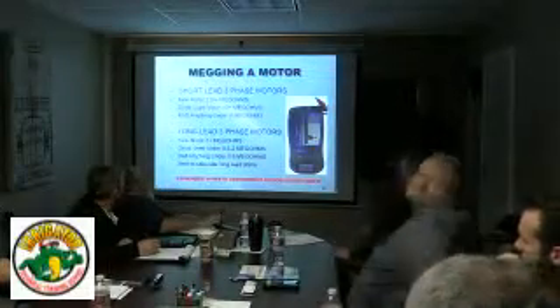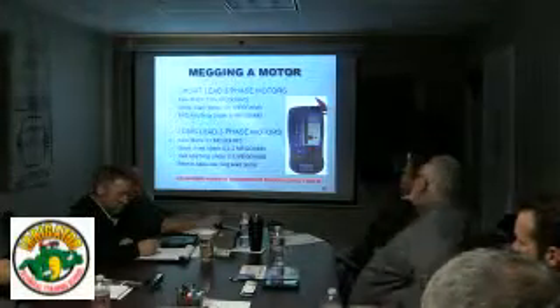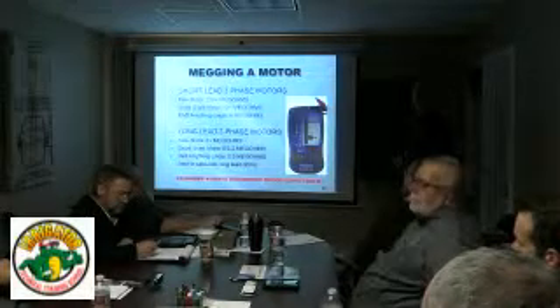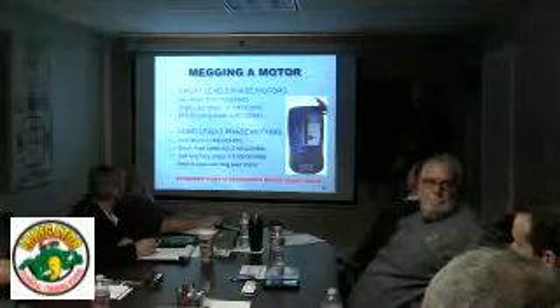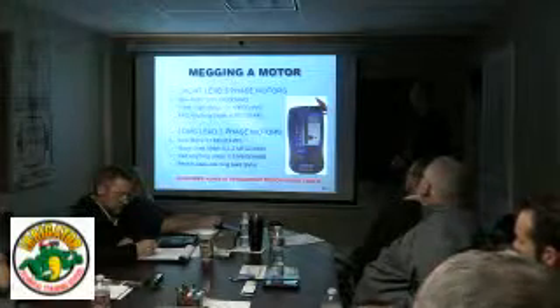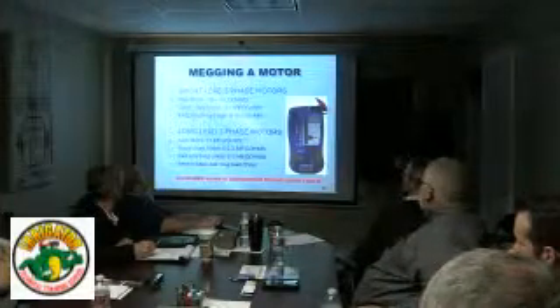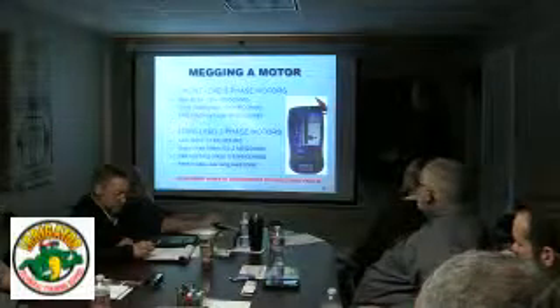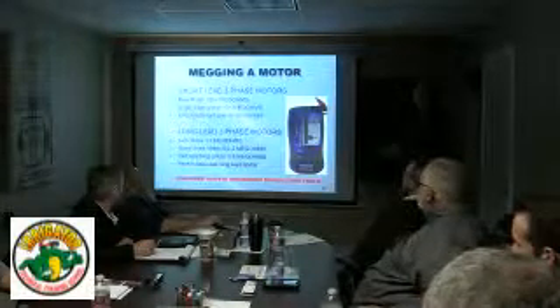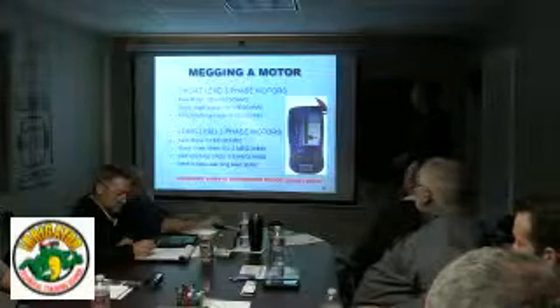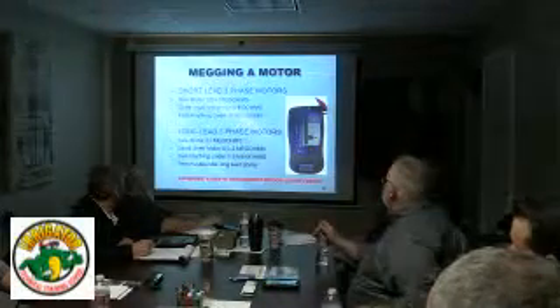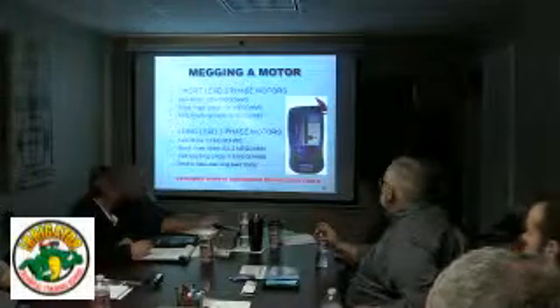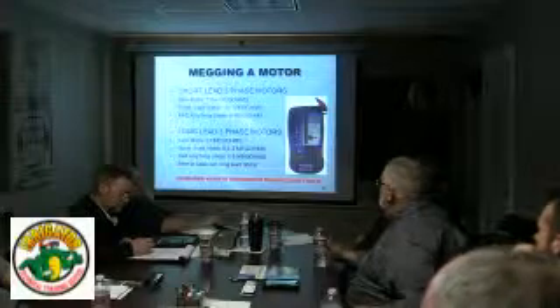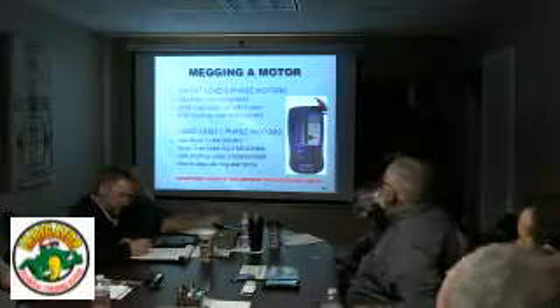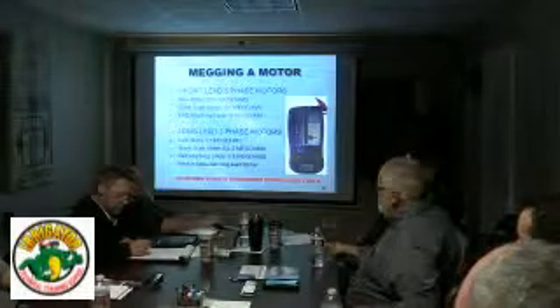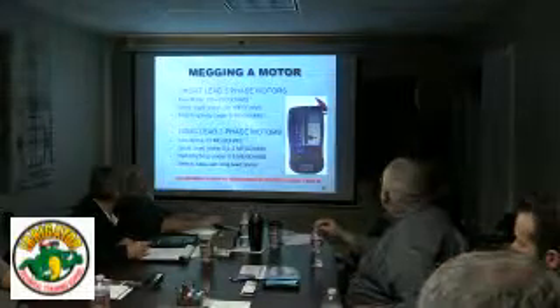When you do meg a motor, if it's submersible down in a well, you do have to take into account those long motor leads, because that's going to affect the measurement. Best thing to do is to find the wire size, the length of the wire, do the calculations, but sometimes that's not possible or it's difficult to do. But these are just some of the general guidelines. A new motor is 200 meg ohms. A good used one would be 10 plus. Anything under 8, it doesn't necessarily mean it's bad, but maybe we just need to look at it farther. Again, with long motor leads, this is just an example. It's really going to depend on how long those motor leads are. For every foot, you're adding more ohms to that reading.